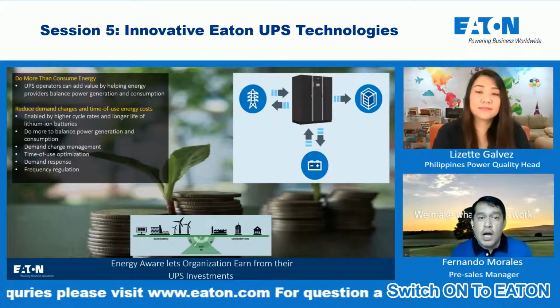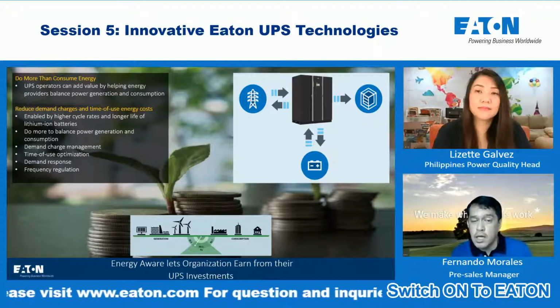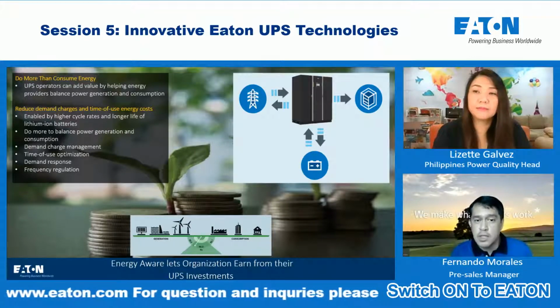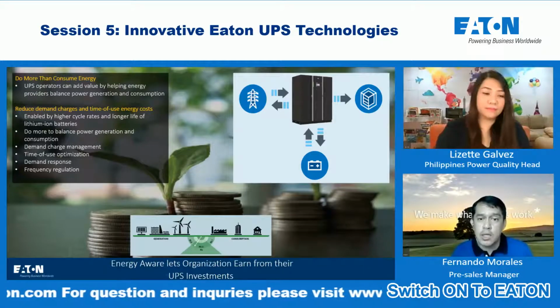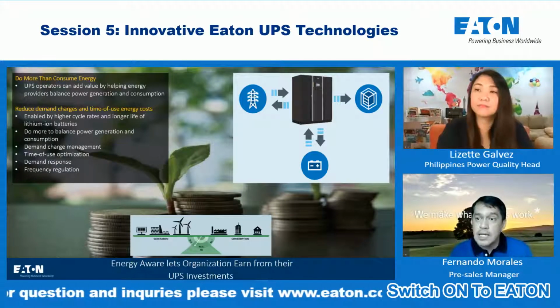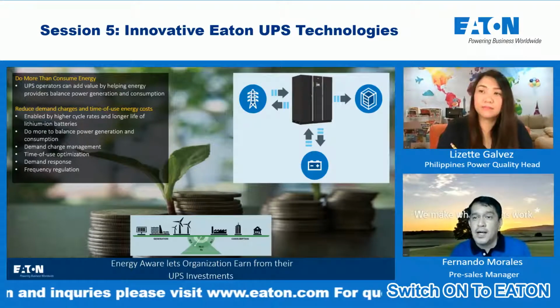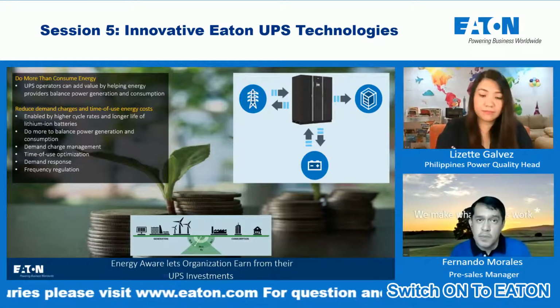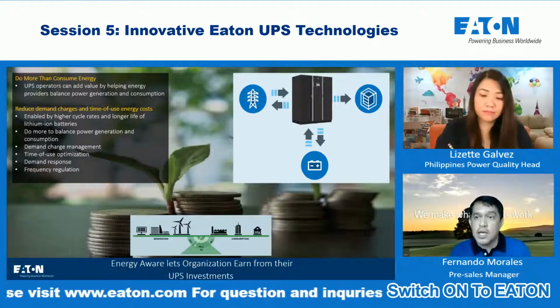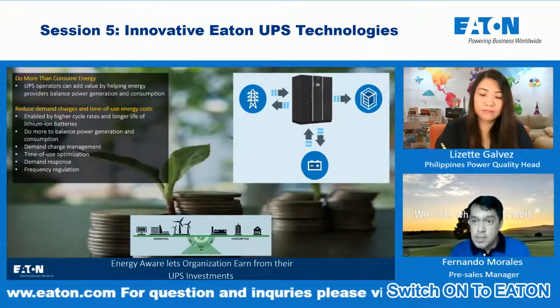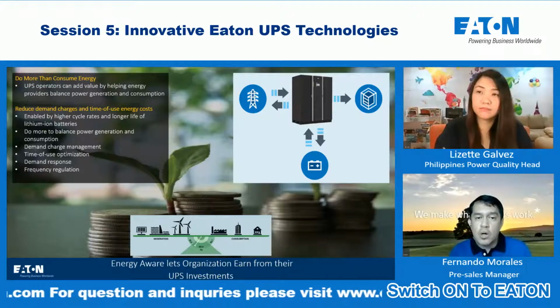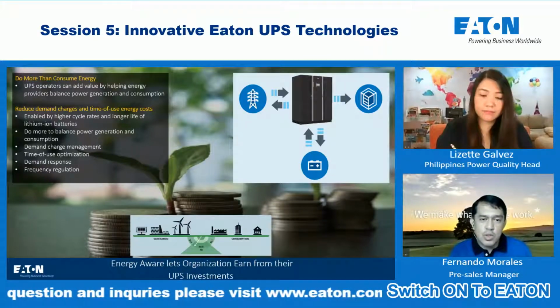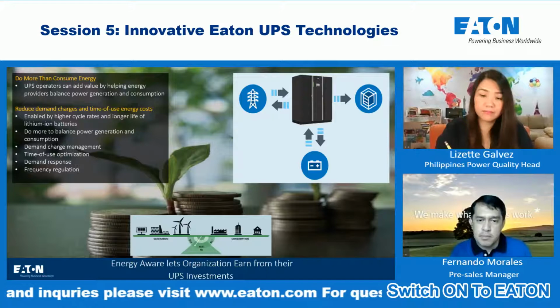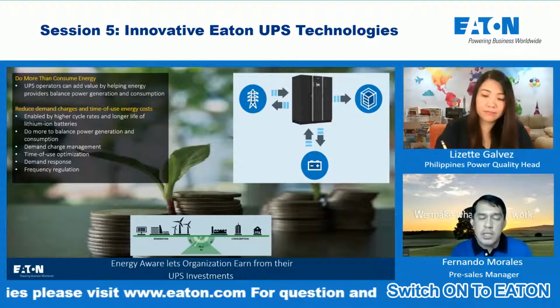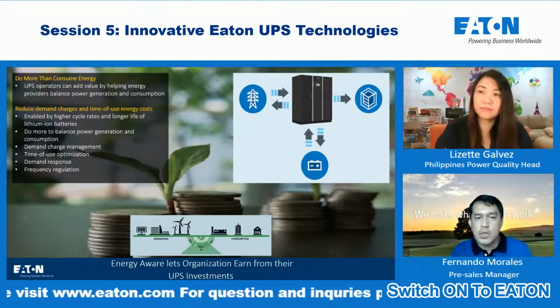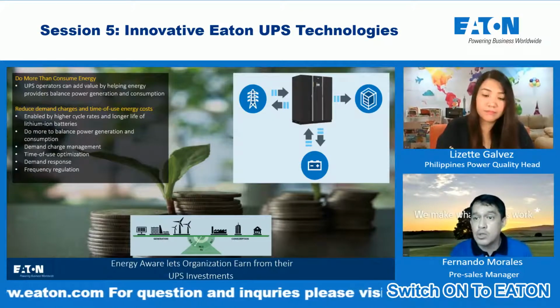So now, if our customer is able to join the frequency regulation feature and help stabilize the grid, they can charge back the utility provider or the power distributor. They can earn a revenue stream using their UPS. Or, if they don't want to join the power stabilization of the grid, they can use their UPS to manage the demand charge or time of use optimization.